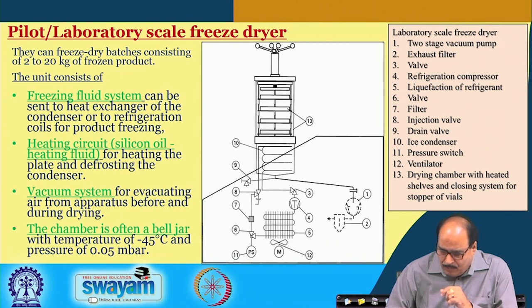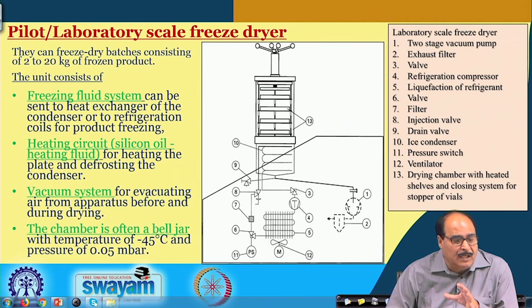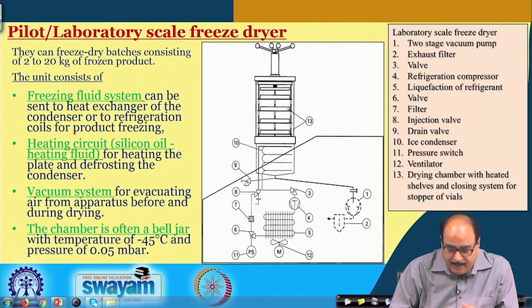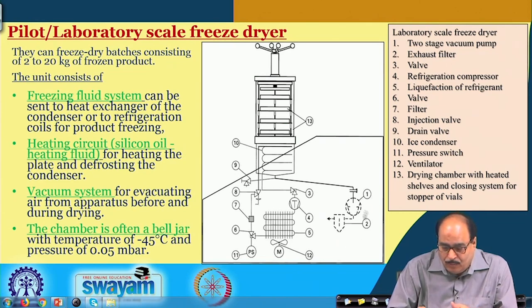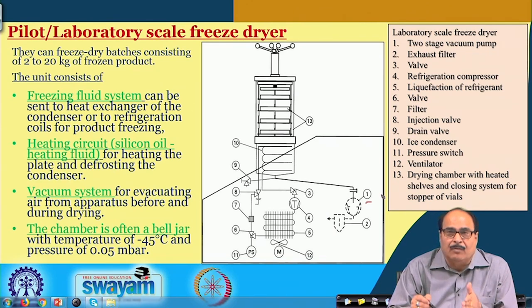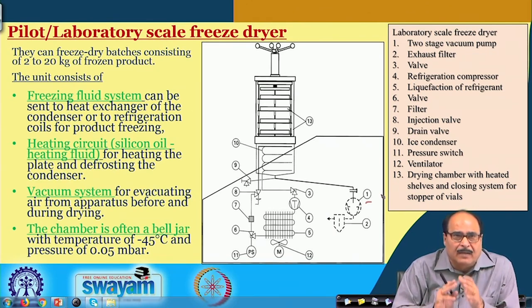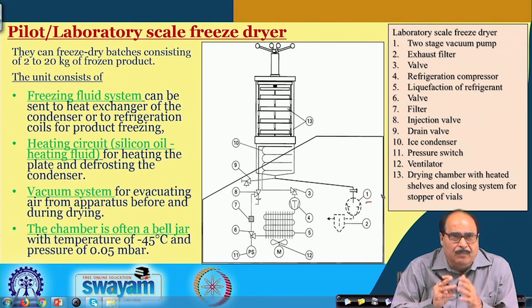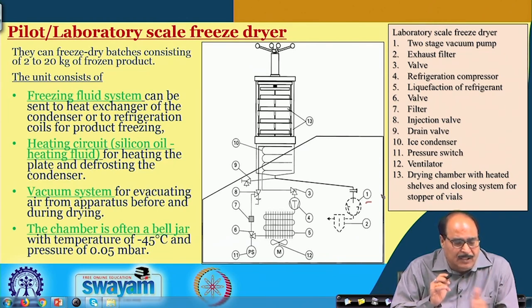In this figure we have shown you the schematic of the laboratory scale or pilot scale freeze dryer. You can see the different components highlighted. It has a two-stage vacuum pump, exhaust filter, valves, and so on. The pilot scale or laboratory scale freeze dryers have a capacity of about 2 to 20 kg of frozen products. The system consists of a freezing fluid system which can be sent to a heat exchanger of the condenser or to the refrigeration coil of the product for freezing.